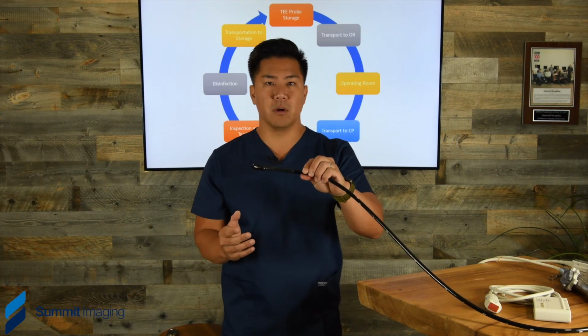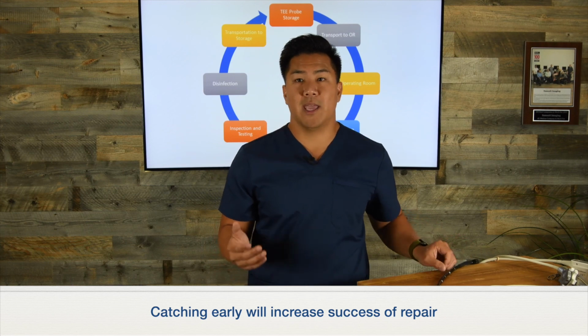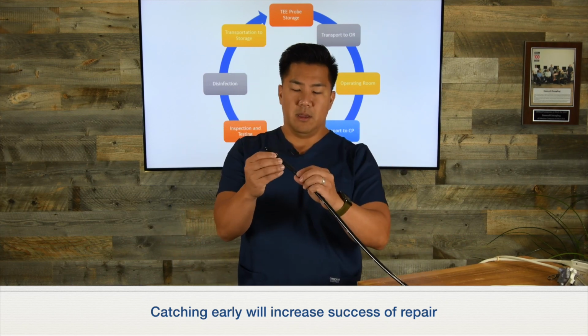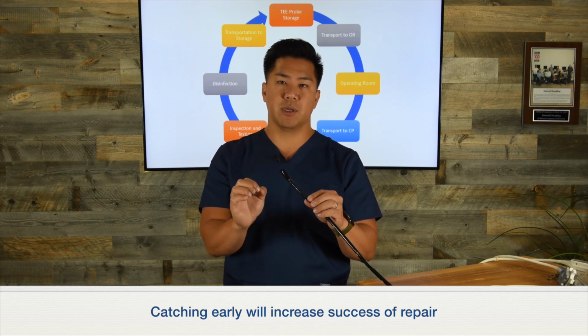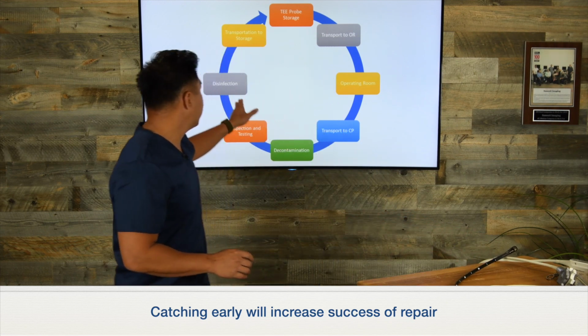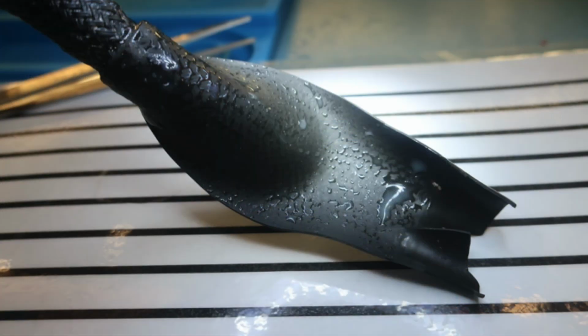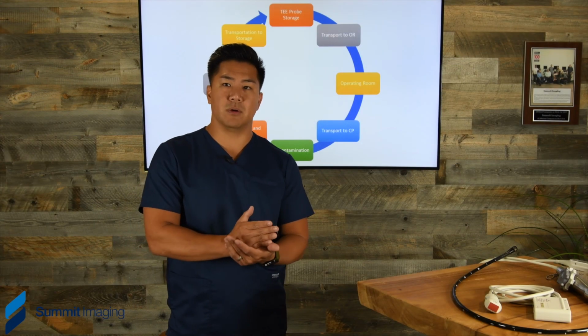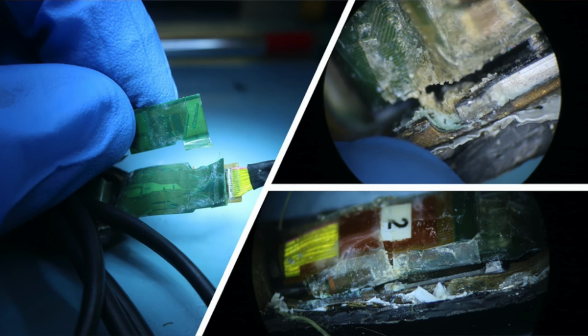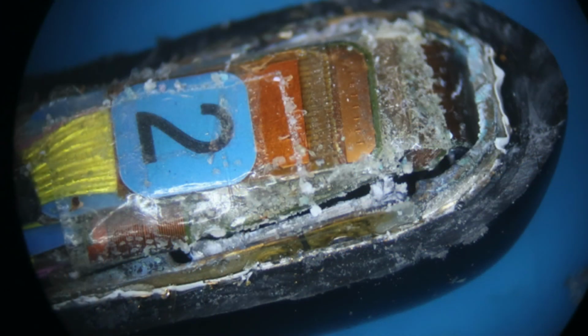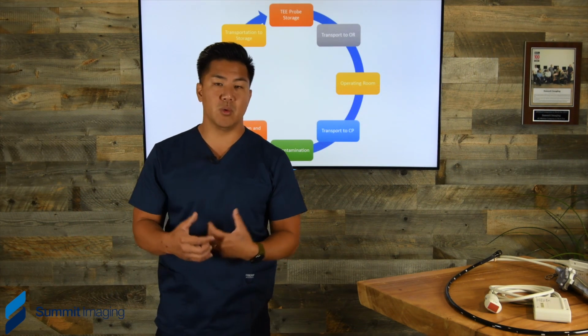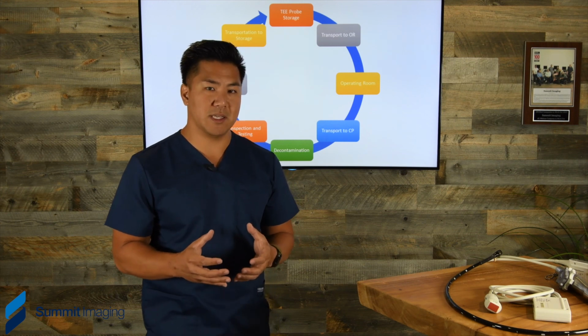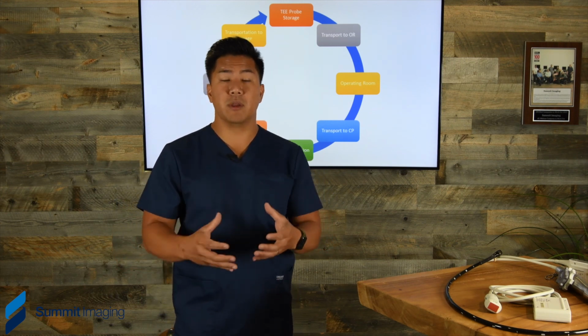And the kind of damage that we see most often is micro abrasions and punctures on TEE probes at this soft bending rubber. Now, we talked about this before. Well, now let's talk about the consequences of not catching it early. If you don't catch these very small punctures, if you fast forward to the next phases of the life cycle, disinfection fluid may get inside these micro punctures. And then it gets stored for a while, and that caustic chemical will sit on the metals of the internals of the electronics of the tip. And then it will degrade and corrode over time. And then, this happens a few times, the corrosion continues to escalate. And the problem with corrosion is that it eats the materials away to where there's literally no materials left.